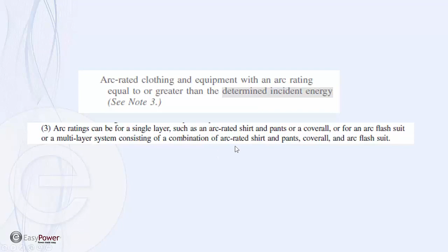All right, now this is the gotcha, if you will, in 2015E, when we start talking about not only how this is done, but how it applies to the labels. And that is the arc-rated clothing and equipment with an arc rating equal to or greater than the determined incident energy. Again, this is for where we've calculated the worst case incident energy. The arc ratings can be for a single layer or for a multi-layer system. Again, it's incumbent upon the worker and the manager to appreciate the fact that we may have an elevated hazard level, and consequently we can put on layers that have been tested and recommended to meet that level of energy. Now when we get to the label, this is straight out of NFPA 70E Article 130.5.